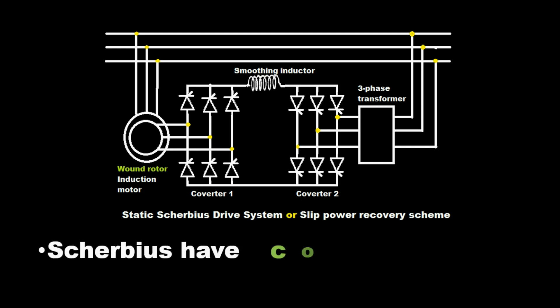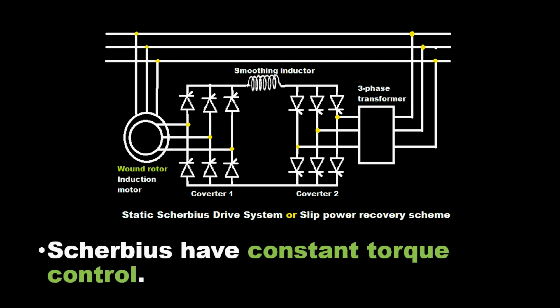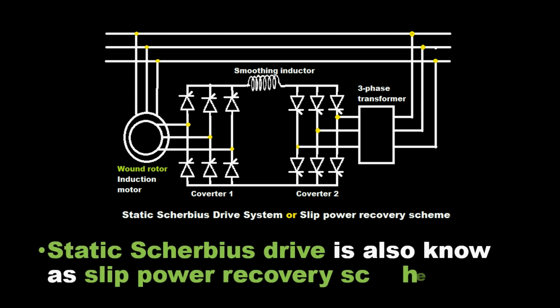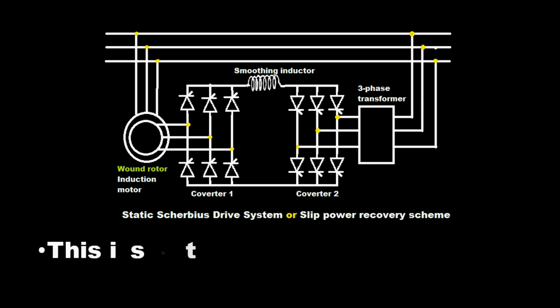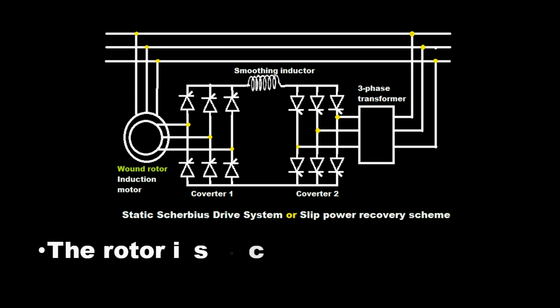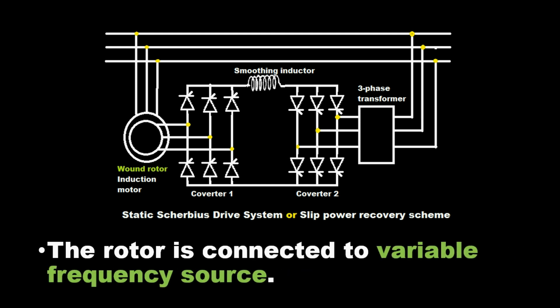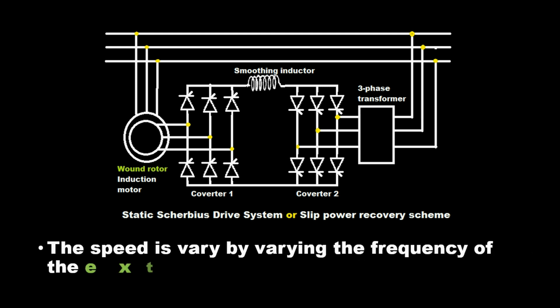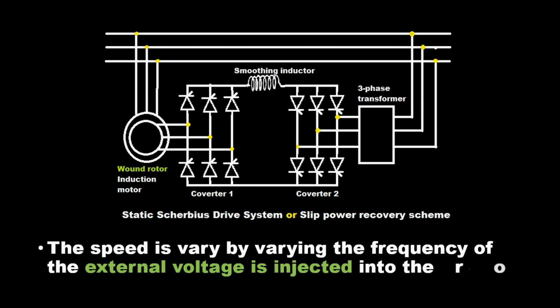The Scherbius Drive provides constant torque control. The Static Scherbius Drive is also known as the slip power recovery scheme. This is a rotor side speed control method, where the rotor is connected to a variable frequency source. Speed is varied by varying the frequency of the external voltage injected into the rotor.